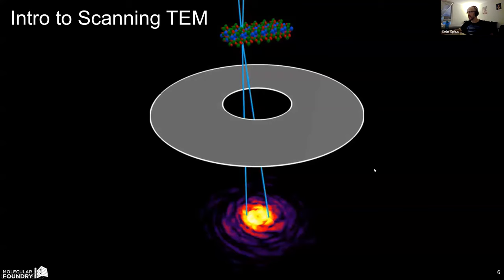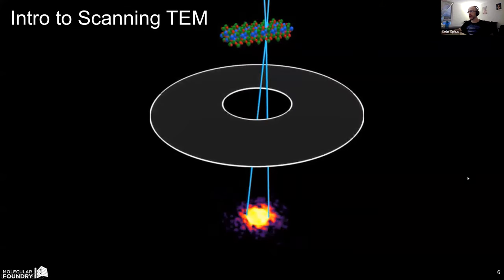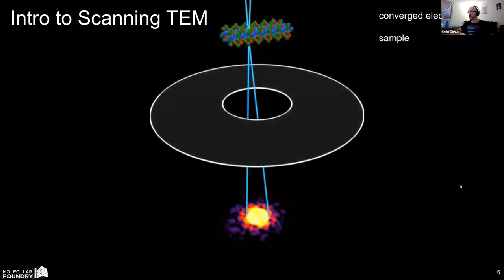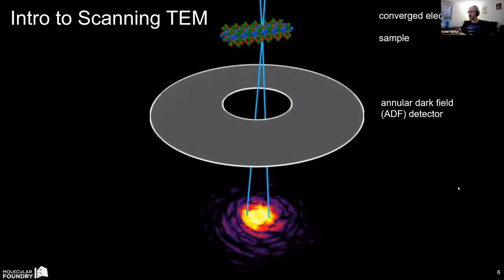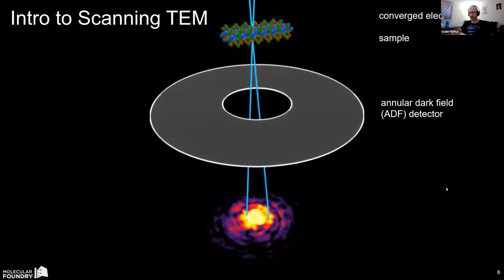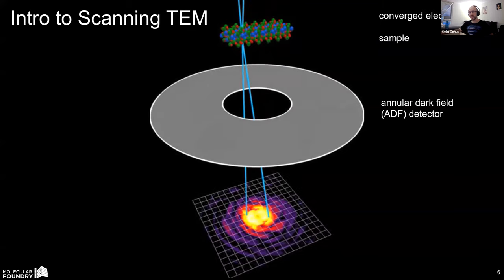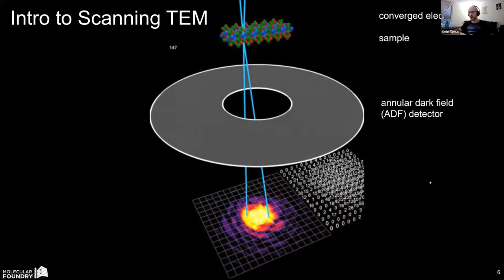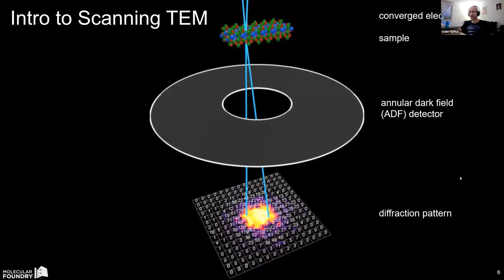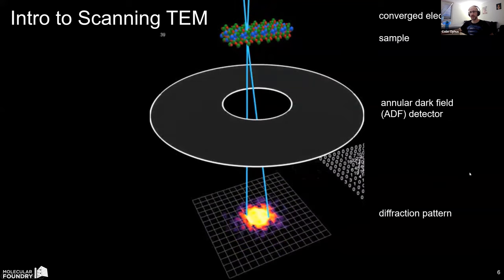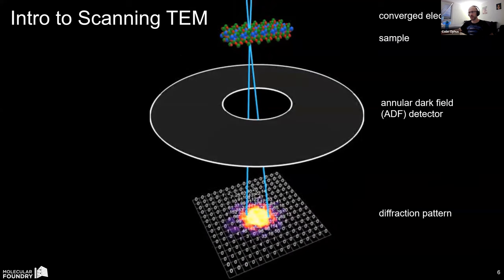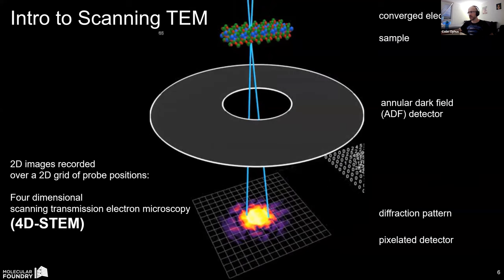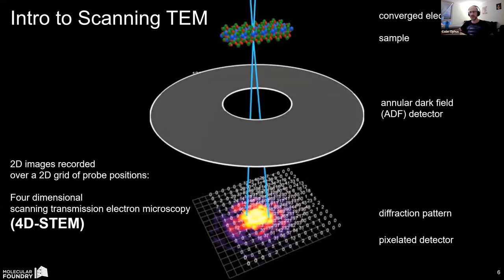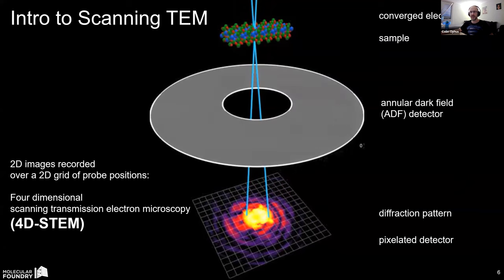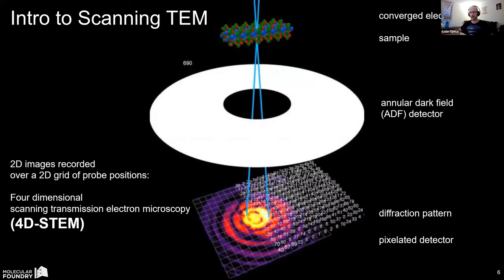So the technique I want to talk about is 4D STEM. Conventional imaging using a converged electron probe passing through the sample used a giant monolithic single pixel detector. We would move the probe to the next position, collect electrons, move the probe to the next position, etc. But these days, our detectors are so fast we can use a pixelated camera, record a full two-dimensional image of the diffraction pattern at every probe position, then step to the next probe position. The result is a two-dimensional grid of probe positions, and at every probe position, a two-dimensional image, giving the name of this technique 4D STEM because of the 4D data.